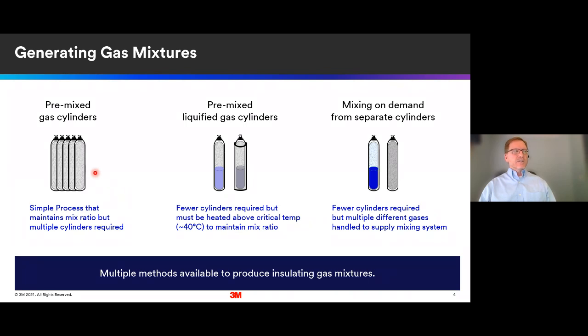This is probably the simplest process, but that larger cylinder does complicate things because you only have a limited amount of gas that you could put into a cylinder and be certain that there'll be no condensation ever prior to using that material that could disrupt the mix ratio. An alternative to that is you could also pre-mix the gas, but allow some of it to be liquefied intentionally. So this would greatly reduce the number of cylinders because now you're able to put a lot more material into a given cylinder. But the requirement would be that this cylinder would have to be heated in order to make certain that you're getting the correct mixing ratio that was intended to go into the equipment.